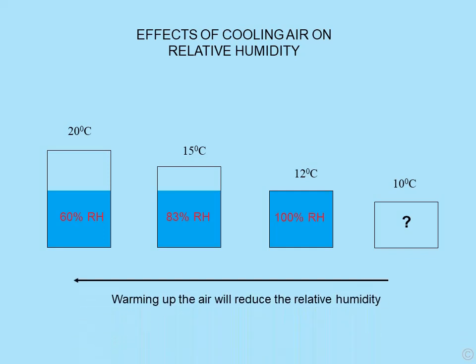The important thing to bear in mind is that warming up the air will reduce the relative humidity. So in a very cold, unheated or poorly heated environment, we could easily have a high relative humidity, but heated up to a reasonable temperature for living, that relative humidity will go down to a very reasonable level.